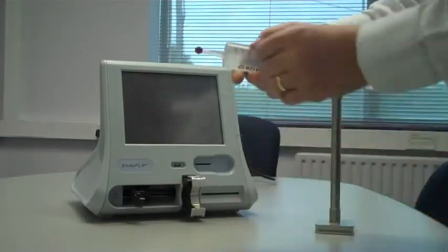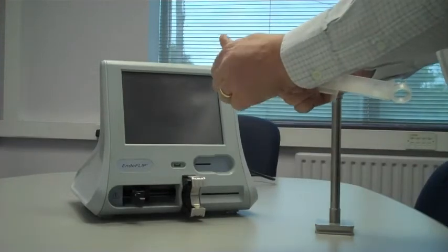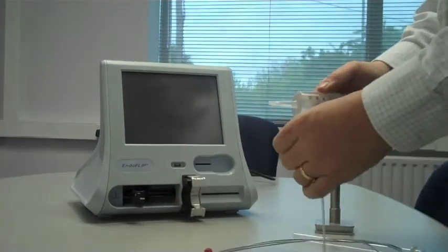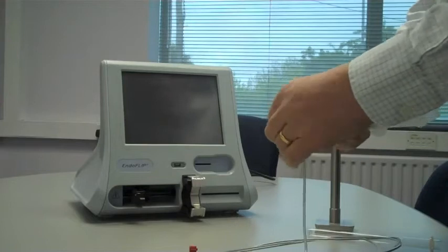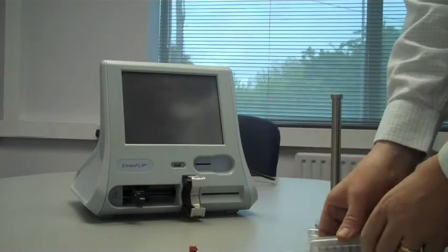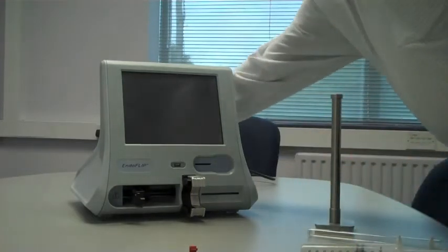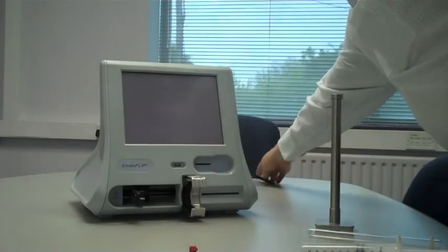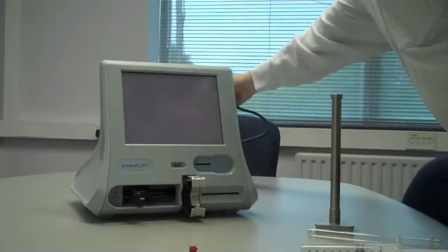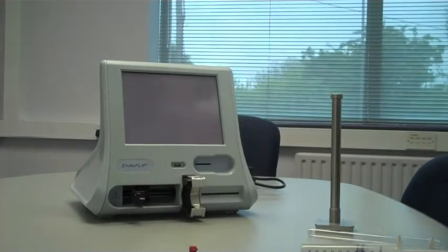Next, you want to take the cap off the syringe and connect it to the lower connector on the catheter, like so. The machine is then switched on. It's connected via this power brick to the wall, and it's important that you have nothing connected to the machine when you are powering it up. And indeed, the first message you will see when the machine powers up is that nothing should be connected.